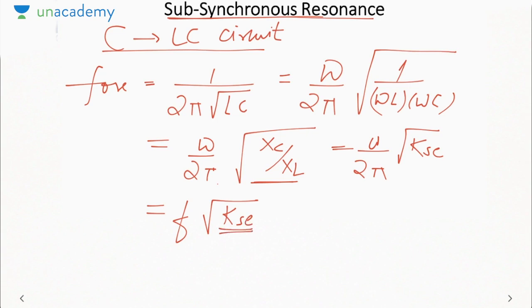Now the degree of compensation will always be less than 1 because we want to reduce the voltage drop. We are reducing the reactance, but we do not want to make it negative, because if Xc is greater than XL, then the reactance XL minus Xc will become negative, or it will become capacitive. Then there will be overvoltages in the system. But overvoltages as well as undervoltages are undesirable. So we want to reduce the voltage drop. Hence, Xc will always be less than XL. So this frequency will be less than F. This is called the subsynchronous frequency because F is the synchronous frequency, which is 50 Hz.